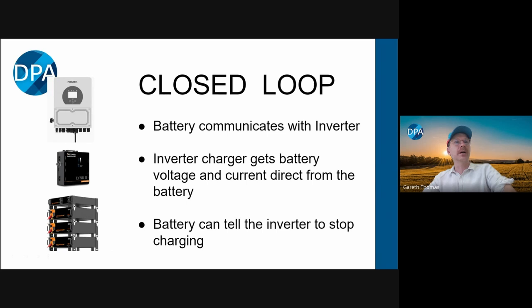It also allows you to pass communication to the inverter, which then goes on to that inverter's monitoring platform. So if we're talking about Victron, for instance, you're going to get not just what the Victron inverter thinks the battery voltage is, you're going to get what the battery thinks the battery voltage is and what it thinks its charge current is, as well as any warnings and alarms the BMS sends through, and maximum and minimum cell voltages. All of that is available in the Victron portal.